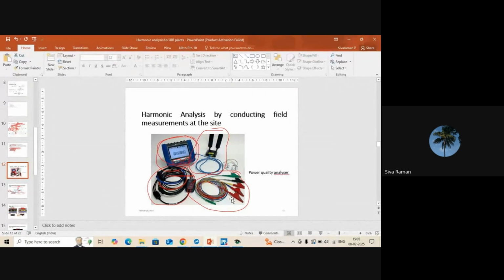So in the analyzer, there is a scale factor based on the CT ratio. We have to enter the CT and PT ratio. For example, with a 100 ampere CT in the primary and 5 ampere in the secondary, we have to enter 100 by 5 in the scale factor. 100 by 5 is 20, so whatever value it reads, it will multiply by 20 and record it.